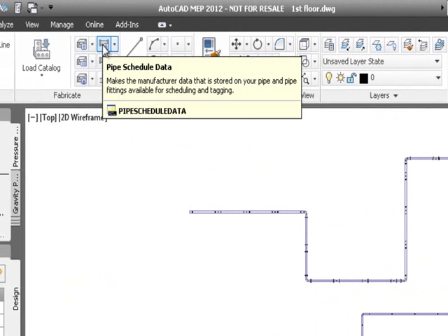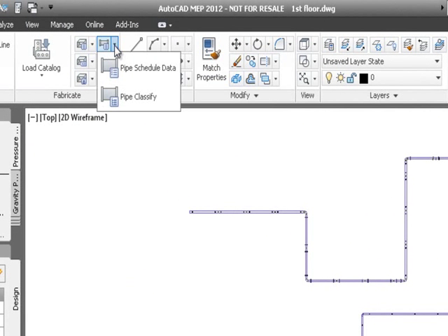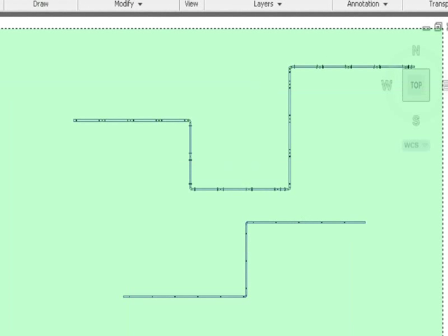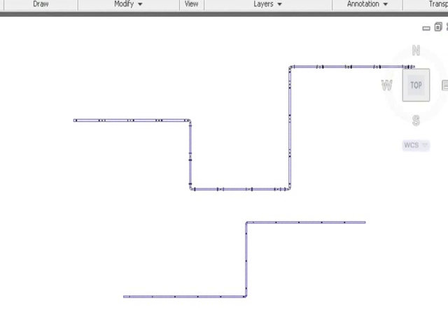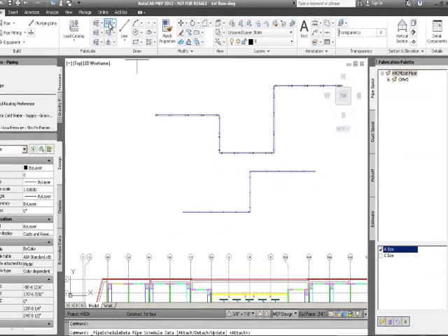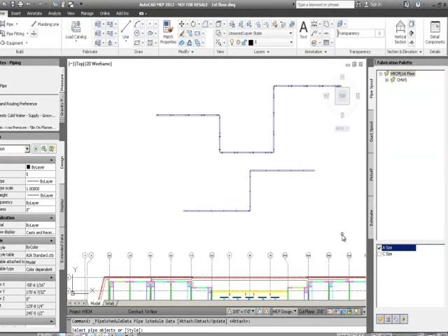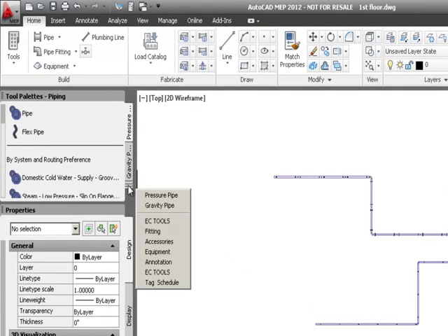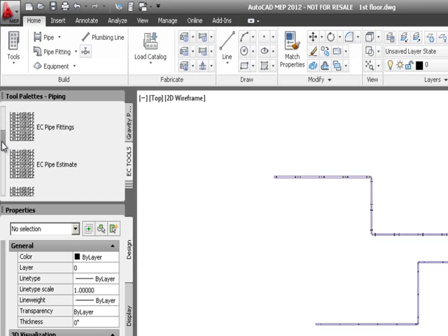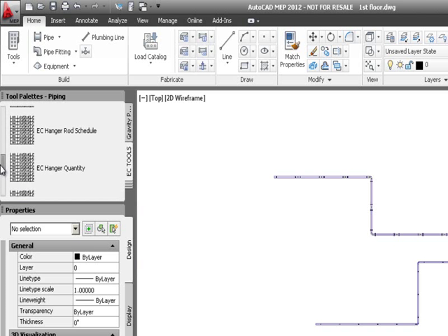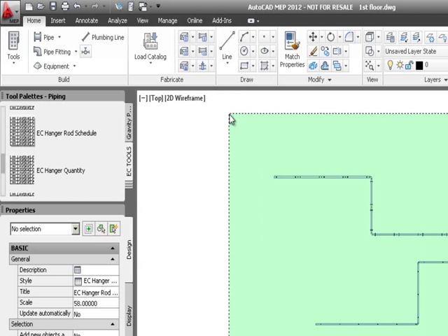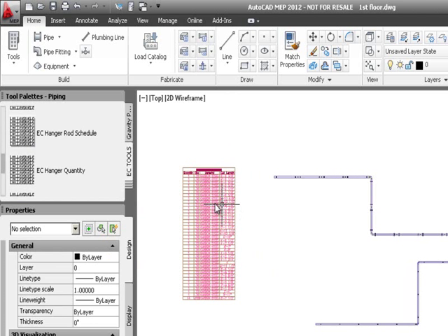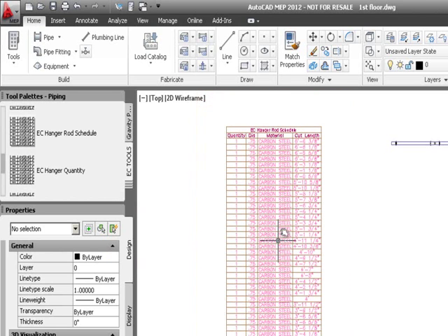Using the Pipe Classify command, I classify all the pipe, which separates the rod from the pipe. I then schedule all data for all pipe in the drawing by selecting all. Coming back to the palette and going to EC Tools, I run the hanger rod schedule, bringing in each different cut length of all the hanger rod.